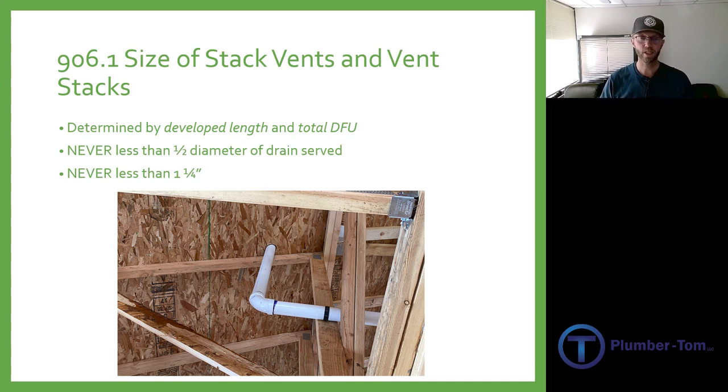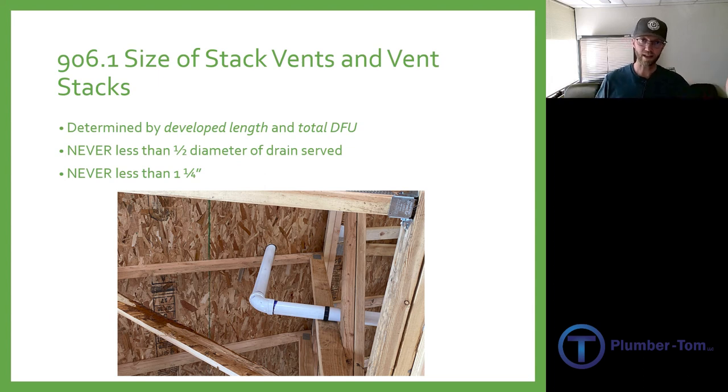We'll start in Section 906.1 where it talks about the size of stack vents and vent stacks. There are a few things you need to know in order to determine the size. First, you need to know the developed length of that vent pipe — from where it connects to the drain to where it terminates. Then you also need the total drainage fixture units for the drains being vented. In order to size vents, you need to know how to size drains. If you're not familiar with drainage fixture units, go back and view the presentations from Chapter 7 before getting too deep into trying to size vent pipe. But with an understanding of drainage fixture units, you'll do just fine.